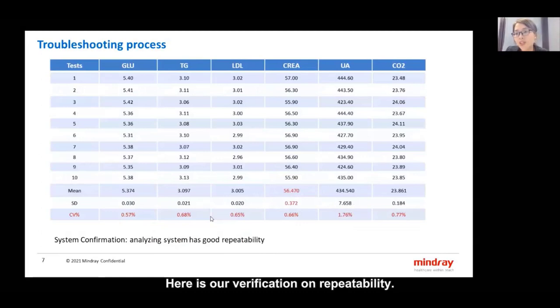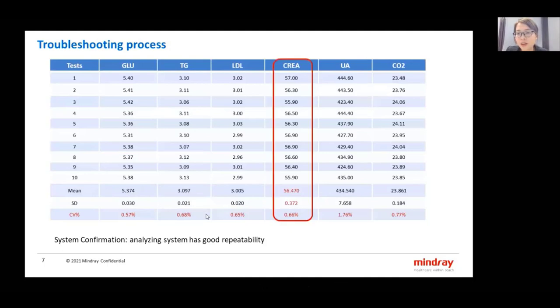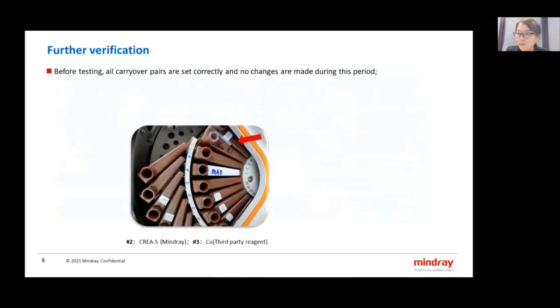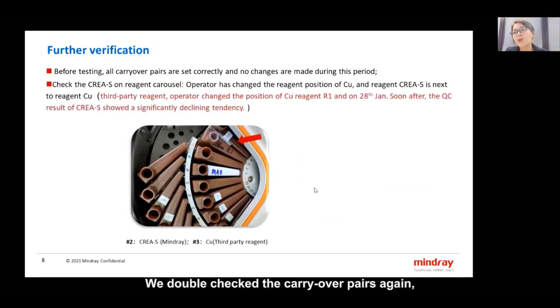Here is our verification on repeatability. We tested each chemistry on each sample, and the CV% is less than 4%. It shows that this analyzing system has good repeatability. Until now, everything seems okay, right? So we did a further verification. We double checked the carryover pairs again, and all carryover pairs are set correctly and no changes were made. But when we checked the creatinine reagent on the reagent carousel, we got important information.